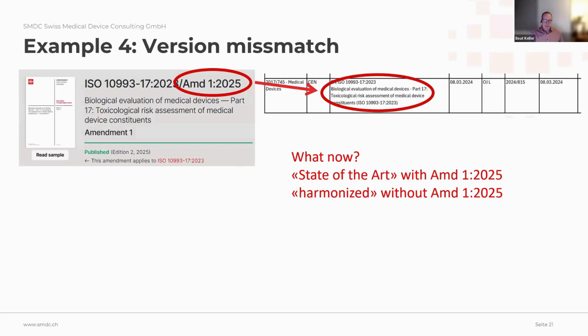Not every notified body sees it the same way, but in fact, usually as soon as you have a newer version, the MDR always says you need to be state of the art. They expect you to go with the newest version. The most extreme case I have once seen is a client who had an audit about, I think, 5, 6, maybe 7 days after a new version of an international standard was published. And this client got a major non-conformity for not being state of the art, because they had not already adopted the documentation 7 days after the publication. It's for sure quite an extreme point of view, but it existed.